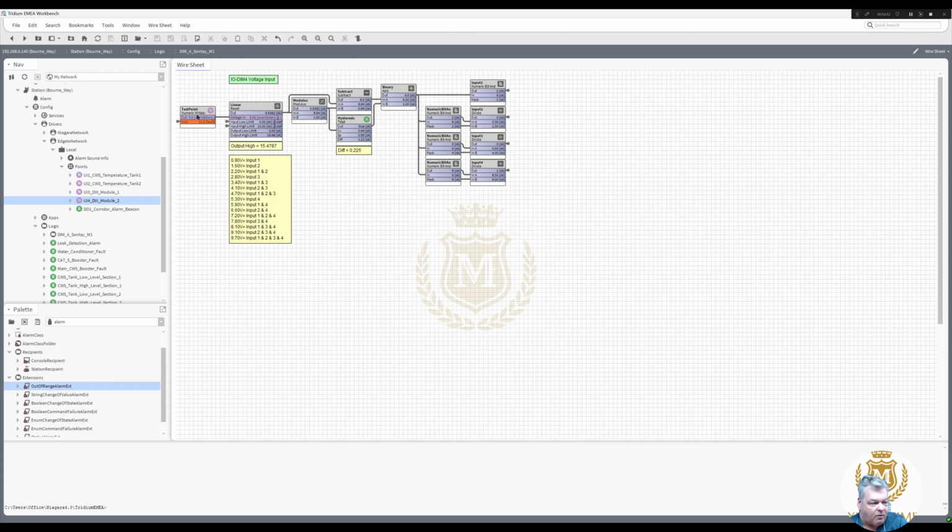That was the simplest way of doing on a Niagara Tridium system the bits for one input and the outputs, unless you know of a simpler way. That's the way that we are using, and I have used on many jobs in the past, and it should be easy for you to copy that logic across.